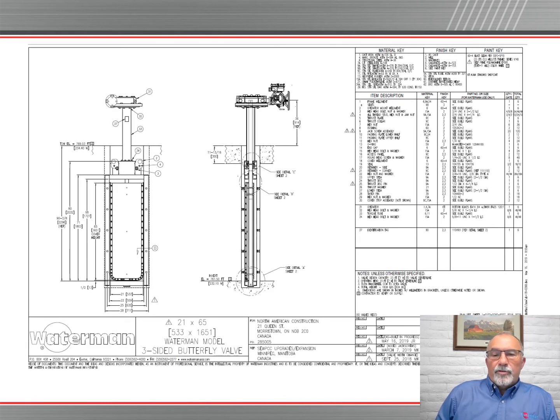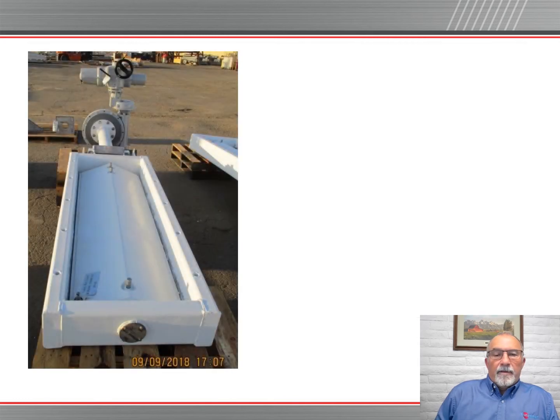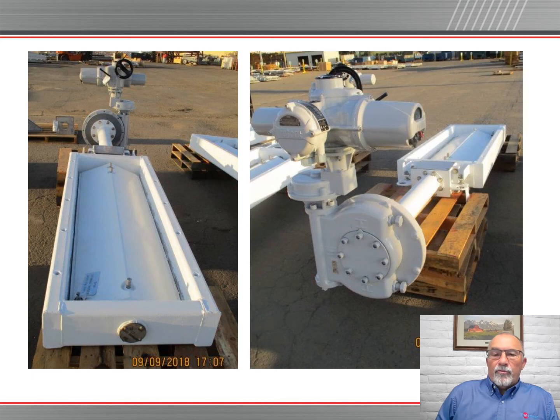There's your drawing, and it shows the parts that we've talked about. That is actually a picture of one of your valves ready to ship from our California plant. And there's another angle with your Rotork operator mounted on the Rotork gearbox. We've been referring to AUMA in the previous slides. They are very similar in design. This one has mechanical stops that are built into those two bolts that come out to the right-hand side. Those are your adjustments for open and closed stop positions. And those are factory set as well, so they shouldn't be something you have to bother with.